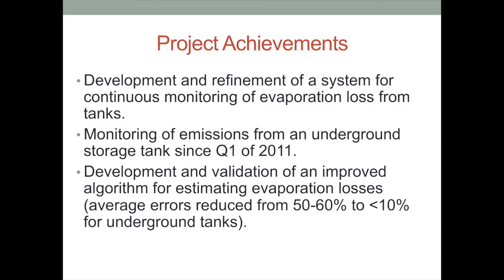The achievements to date include a refinement of the system we initially put on the underground storage tank at the retail service station to overcome some instrumentation issues and provide a more robust and easier-to-monitor array of sensors, which we are now installing on an above-ground storage tank. The above-ground storage tank is going in at a bulk fuel facility, which has a Veeder-Root liquid-level monitoring system on that particular tank, just like the underground storage tank. They continuously measure both the liquid level and the product temperature in the tank so we can correct for thermal expansion and contraction of the fluid.